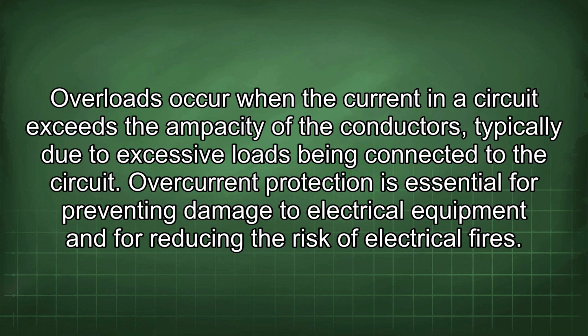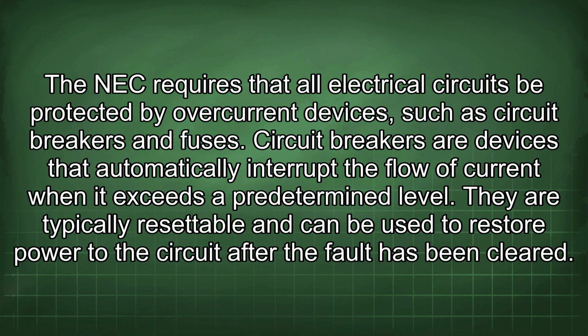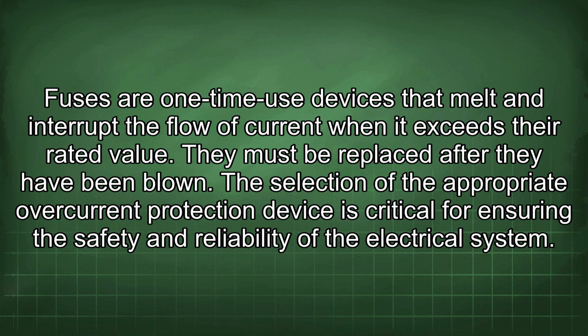Overcurrent protection is essential for preventing damage to electrical equipment and for reducing the risk of electrical fires. The NEC requires that all electrical circuits be protected by overcurrent devices, such as circuit breakers and fuses. Circuit breakers are devices that automatically interrupt the flow of current when it exceeds a predetermined level. They are typically resettable and can be used to restore power to the circuit after the fault has been cleared. Fuses are one-time use devices that melt and interrupt the flow of current when it exceeds their rated value. They must be replaced after they have been blown.